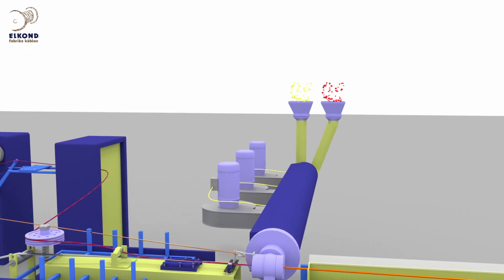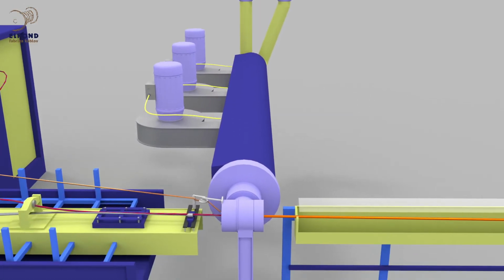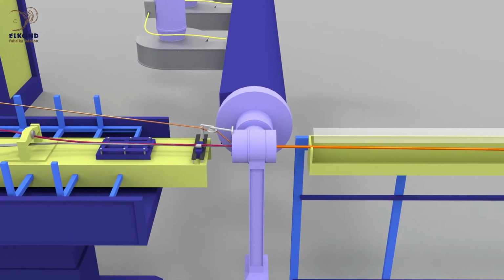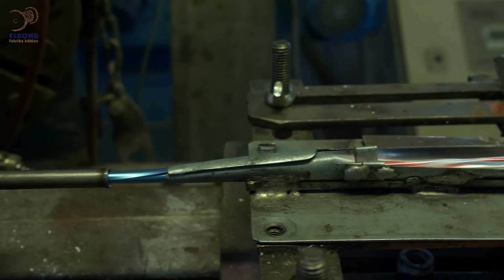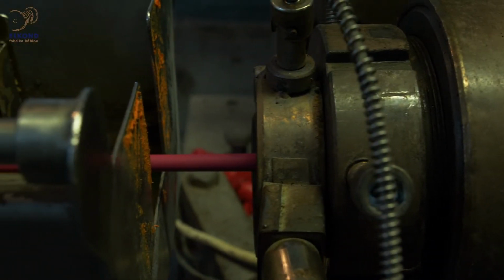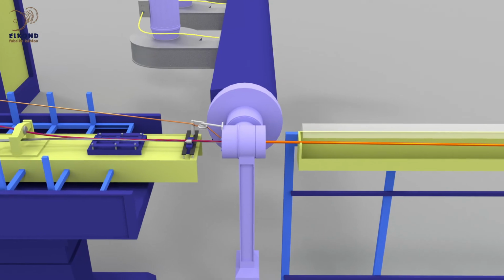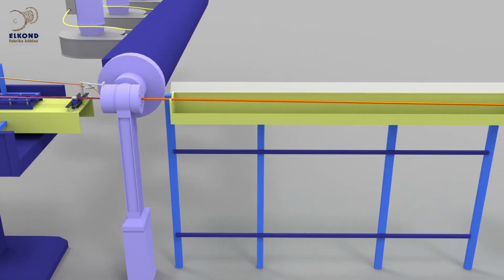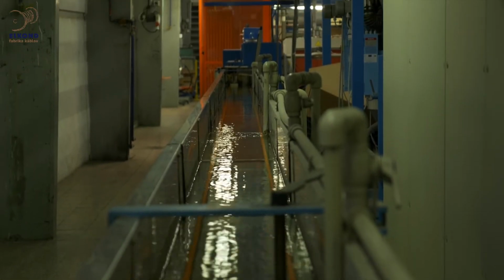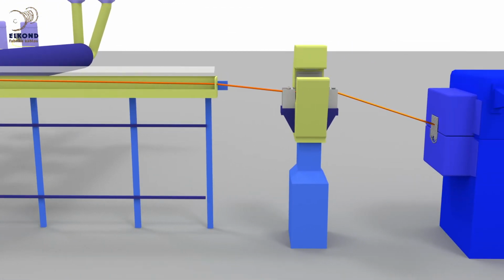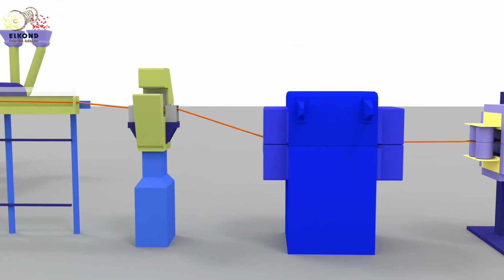The coating itself is done by extrusion heads where the melted compound is applied to the cable core. The outside coat has several functions. It protects the conductors from effects of weather, UV radiation, and mechanical damage. In self-support aerial cables, we use steel bearing rope. After applying the outside coat and subsequent quick cooling, the outside diameter is checked by a laser, followed by a spark tester that verifies the coat integrity.